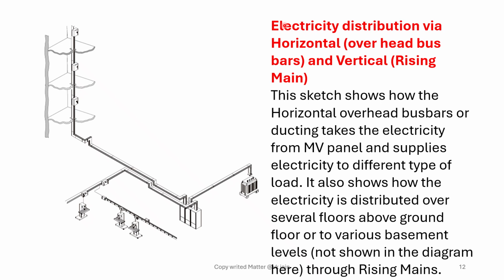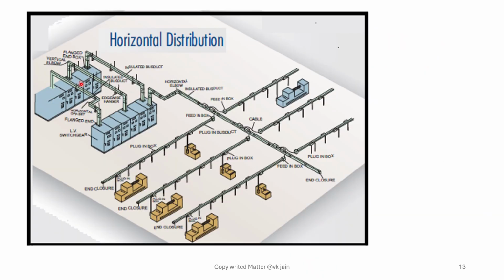Electricity distribution via horizontal overhead bus bars and vertical rising mains. The sketch shows how the horizontal overhead bus bar or ducting takes the electricity from the MV panel and supplies electricity to different types of load. It also shows how the electricity is distributed over several floors above ground floor, to various basement levels, although not shown here. In this isometric view of horizontal distribution of electricity through overhead bus bars from the main panels, a number of panels.